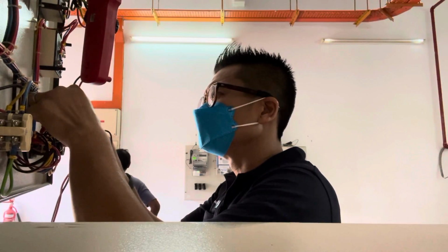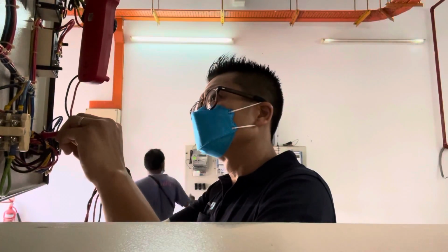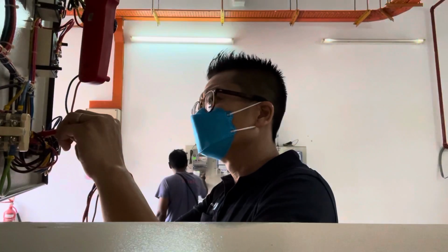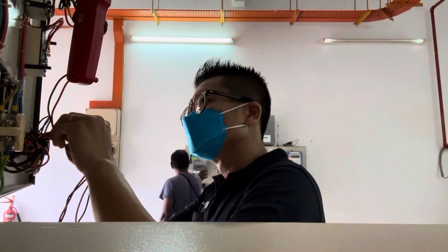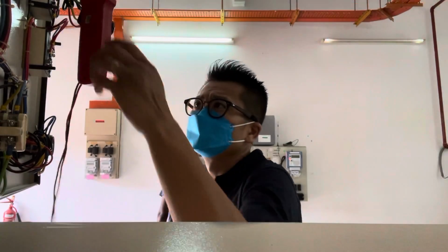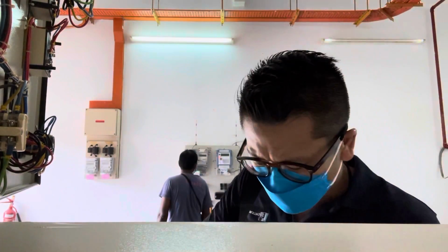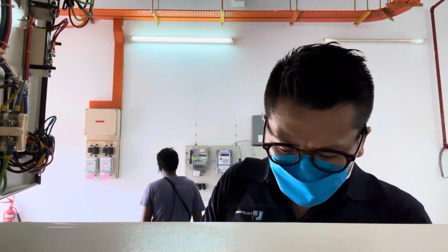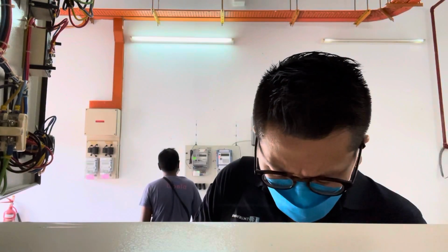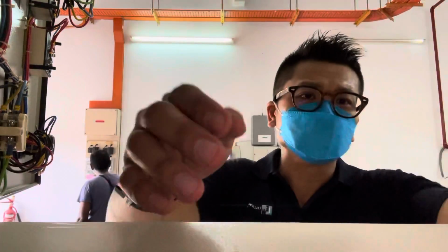Blue phase 244. Three phase: 417, 421, 418. If let's say the three phase voltage is more than 430 or the single phase voltage more than 250, that indicates a high level of voltage. So need to take care, otherwise it will damage the building equipment easily.